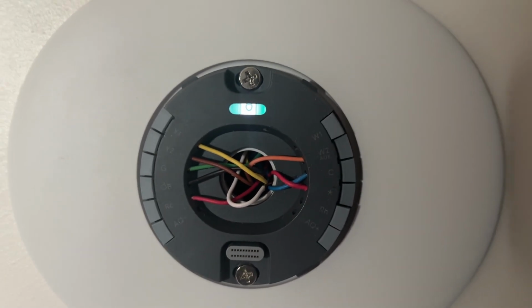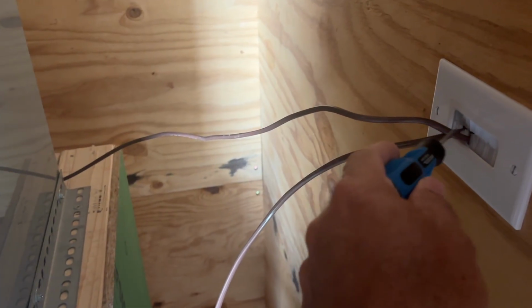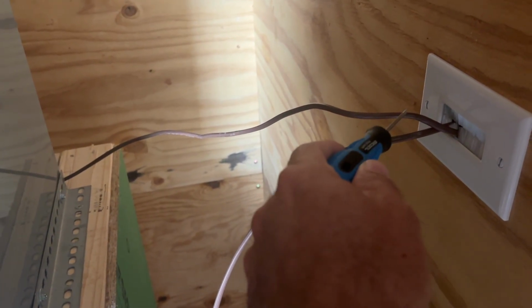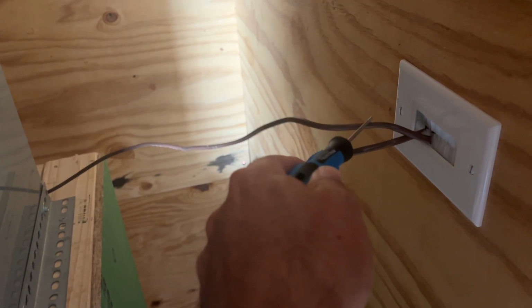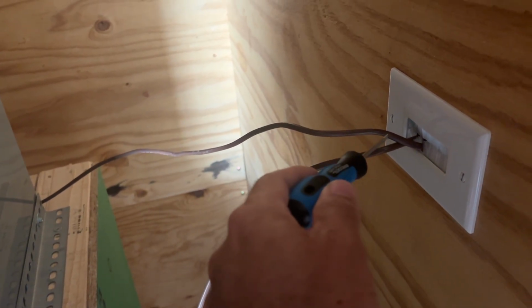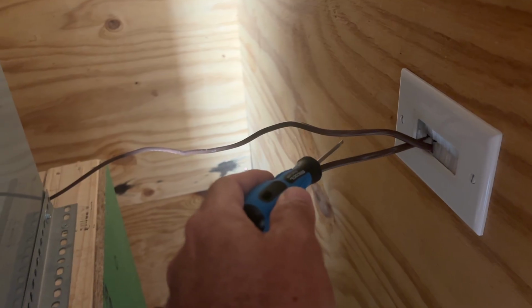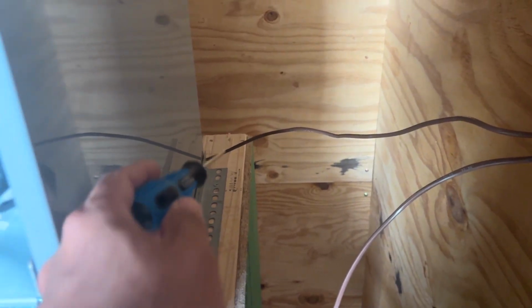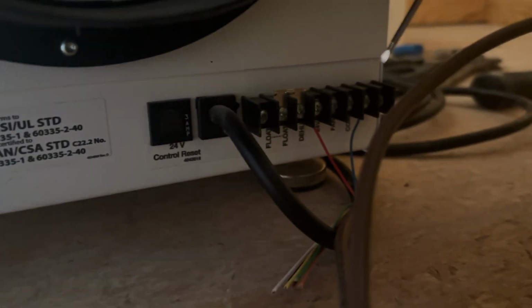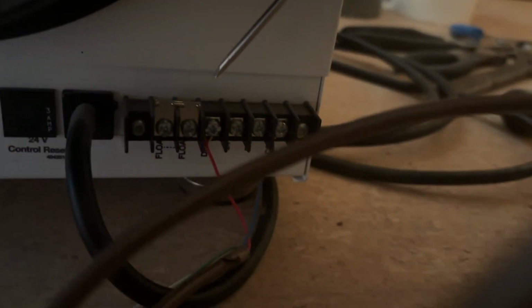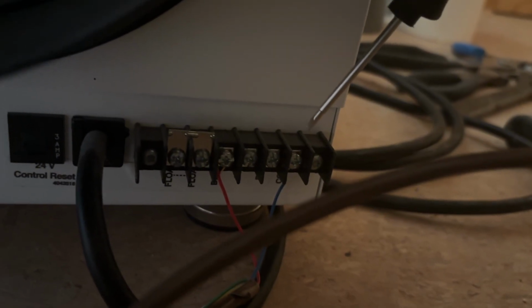So let's go back and look at the dehu. For me, I ran 2 thermostat wires out. I had to buy a spool of the 18/8, 250 feet. So I just ran 2 strands of this, not knowing exactly what I was gonna need. And I'm gonna run the second strand behind the air handler and hook it in to the dehumidifier. And basically on this, it's pretty easy to set up. I have the red wire into the dehu control, and then I have the blue into the common.